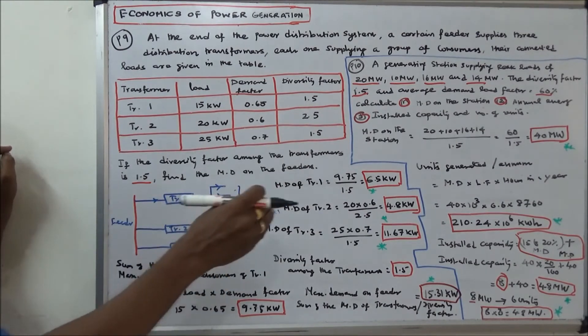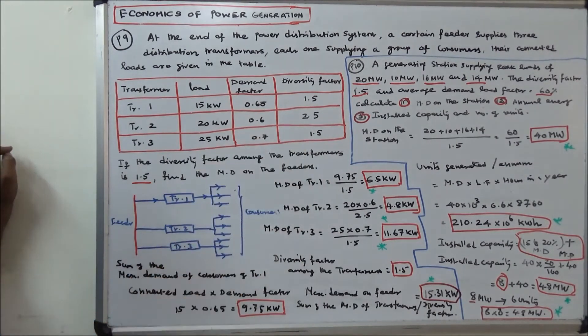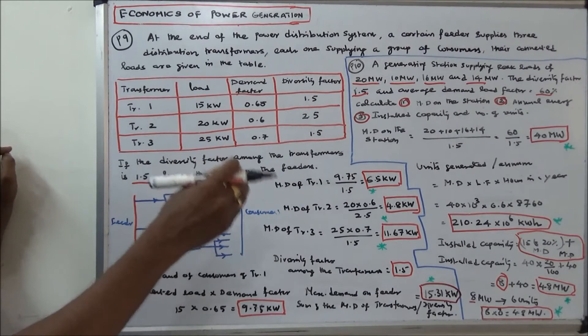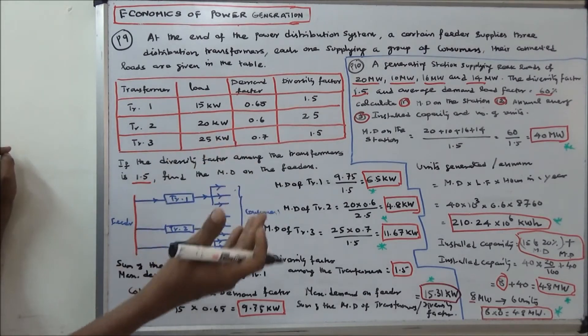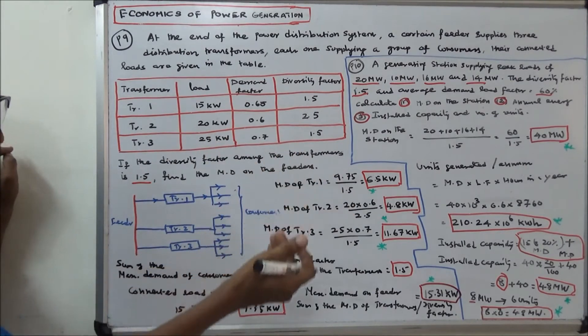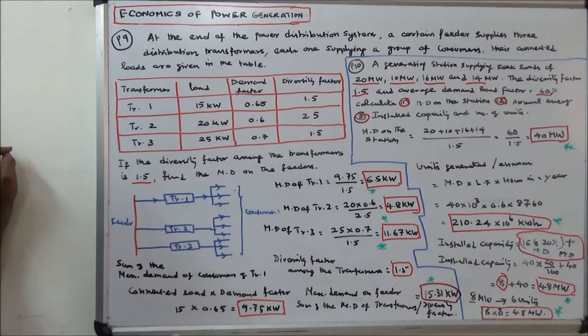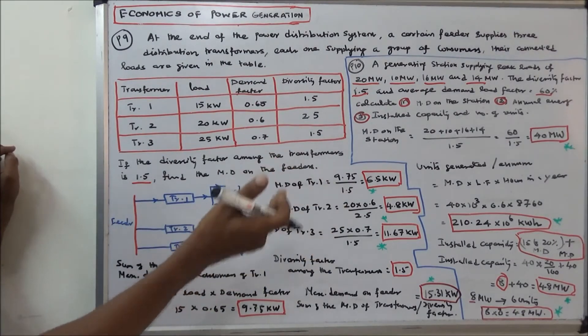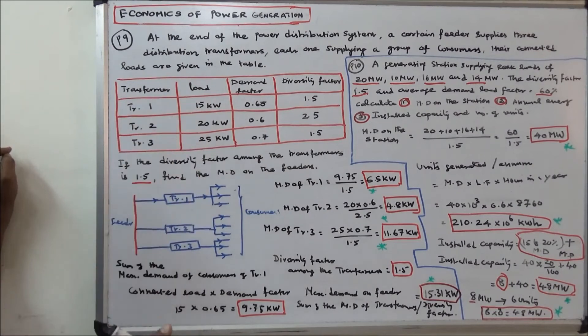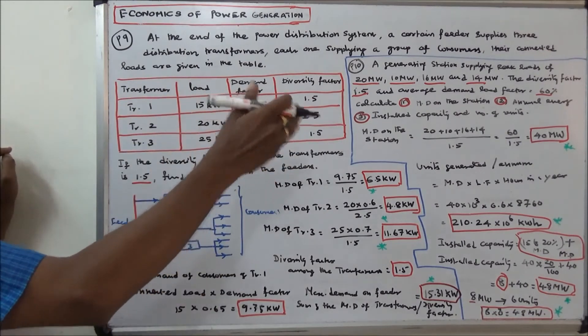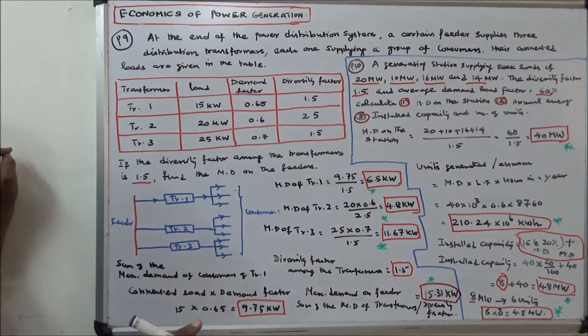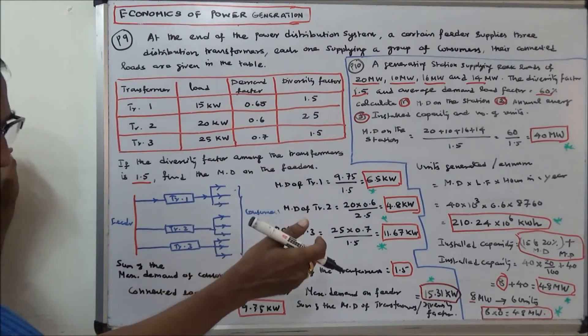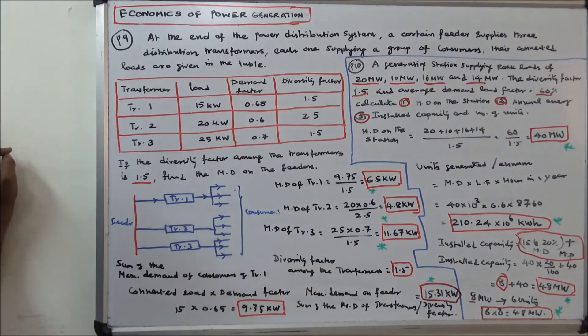Third, we calculate the installed capacity. Installed capacity is 15 to 20 percent above the maximum demand plus the maximum demand itself. Choosing 20%, that is 20% of 40, which is 8. So 8 plus 40 equals 48 megawatts — that is the installed capacity. For the number of units, I choose 6 units, each of 8 megawatts: 8 times 6 equals 48 megawatts.